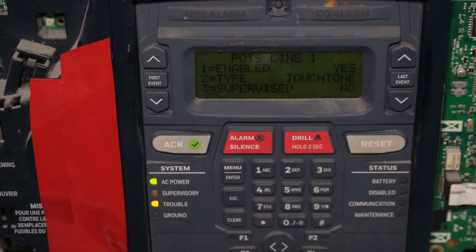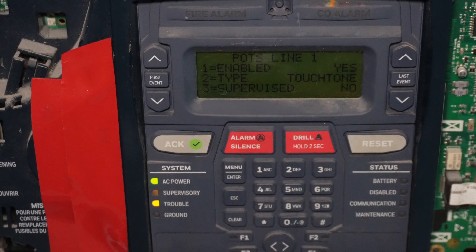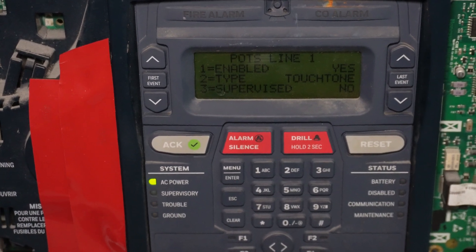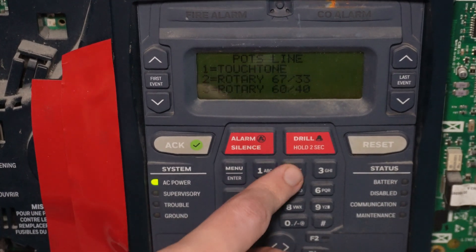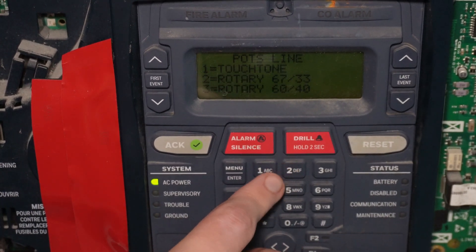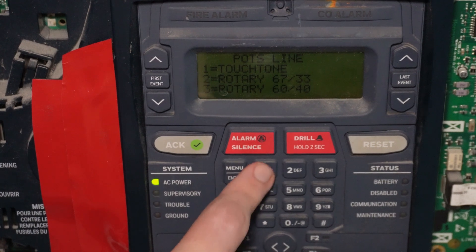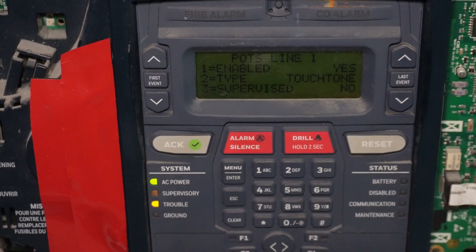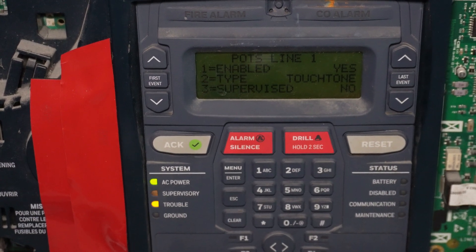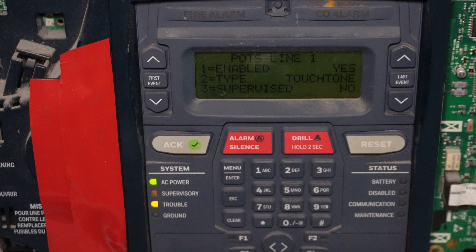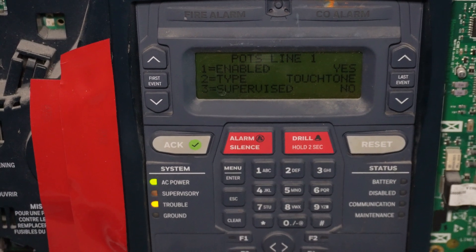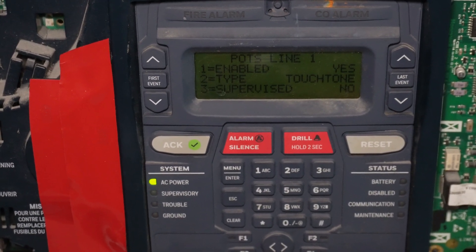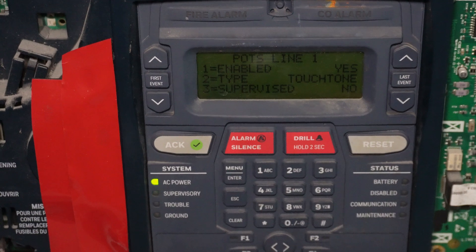Touch tone, yes, that's probably what you want for most modern phone lines. The other option is Pulse, but probably most modern phone providers over landline do not support Pulse dialing anymore. So leave it at touch tone. So supervised, if we turn that on, essentially the panel will just keep periodically making sure that there is voltage coming over the phone line.